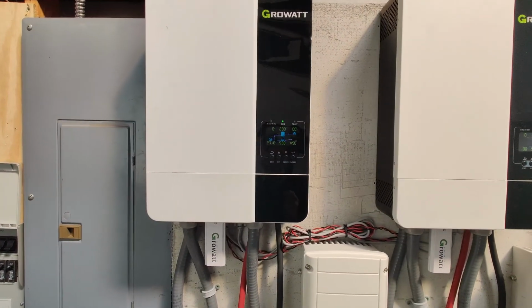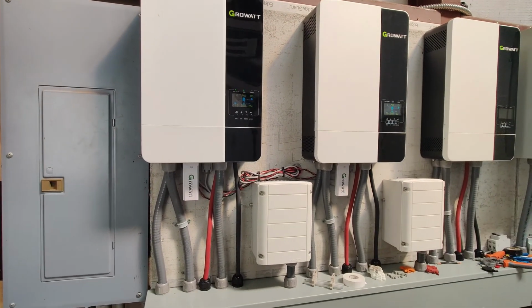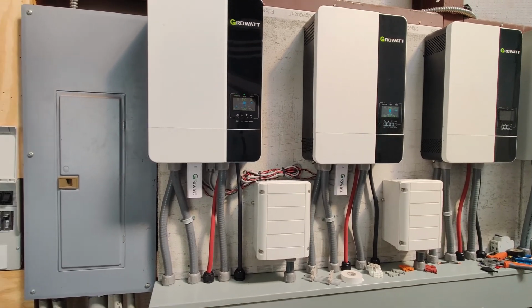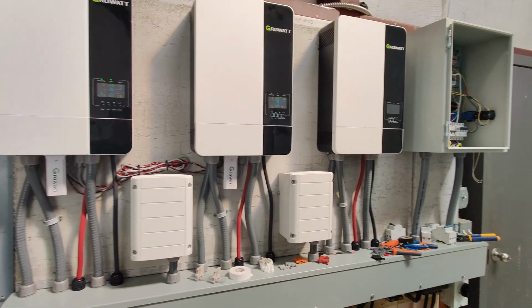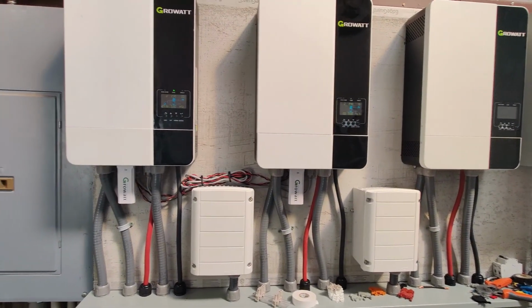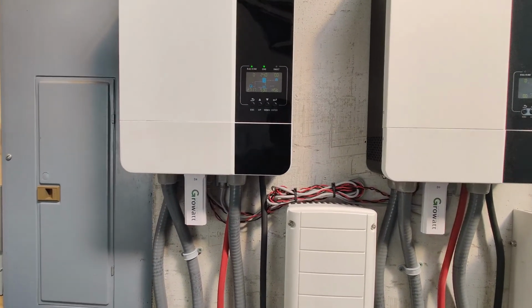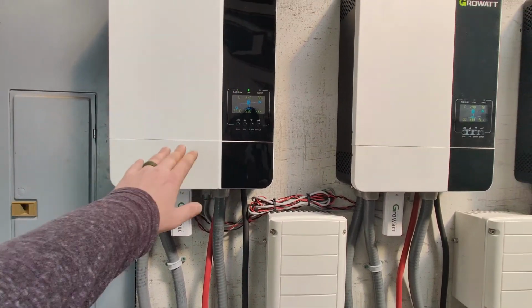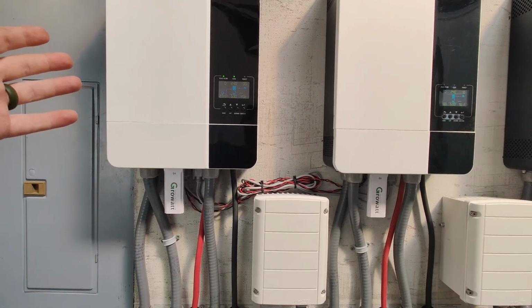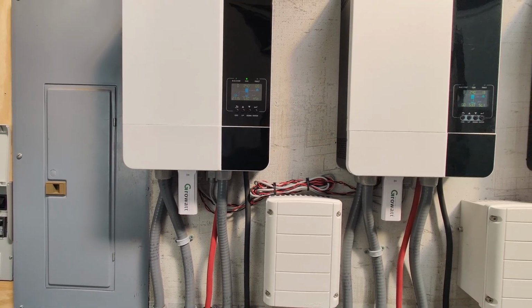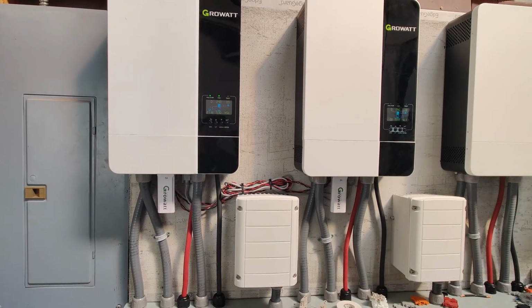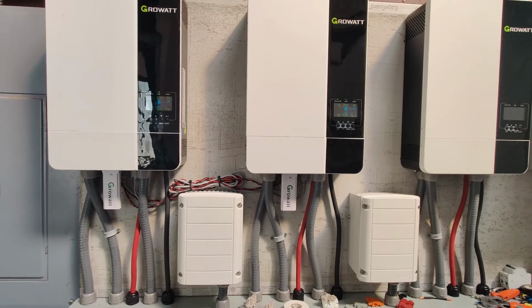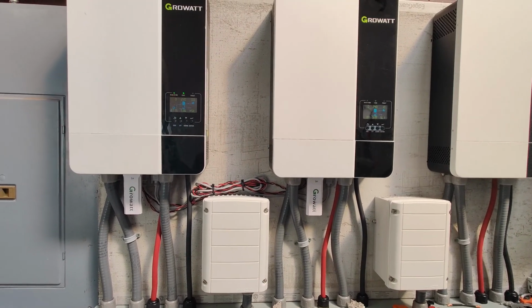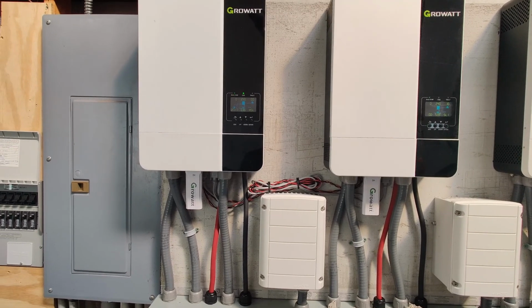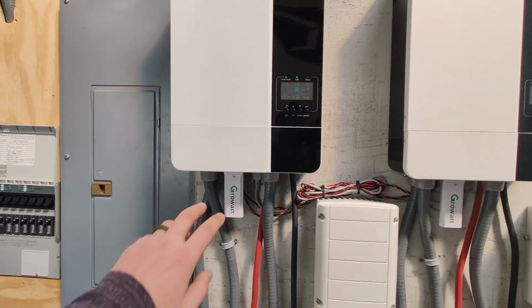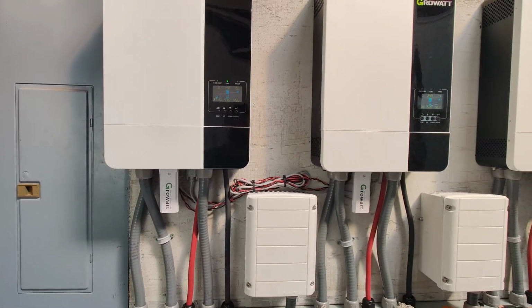As you may or may not know, there's been quite a hubbub on the internet about these inverters, because Signature Solar has created a model of this inverter which is very cost effective and works in the US. If you import them yourself from other places, you could run into a potentially dangerous situation where the neutral leg is grounded to the line leg. That works in Europe, but in North America those cannot be bonded together. That would be very bad.